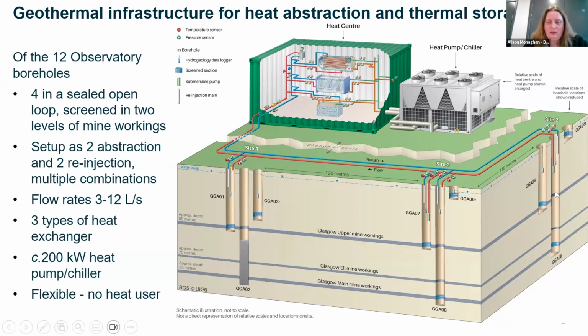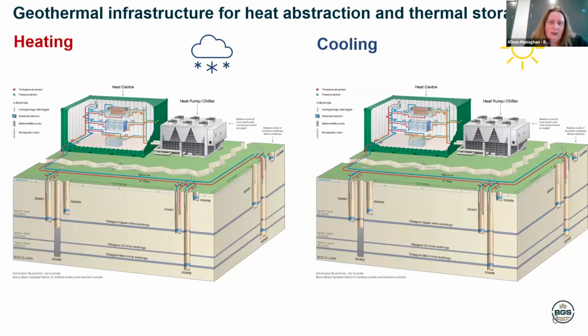The boreholes are fitted, some of them, with submersible pumps, and linked by a mine water pipe which goes to the heat centre. The capacity is that we can pump up to about 12 litres a second from one mine working into another, or between the same mine working. The facility enables us to do either heating or cooling of that mine water, to study the subsurface responses and the responses of the surface infrastructure.